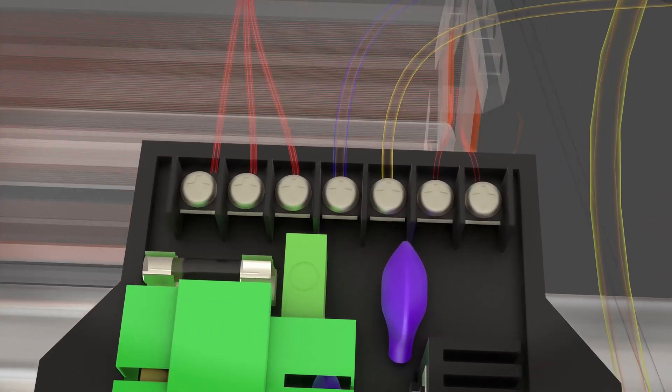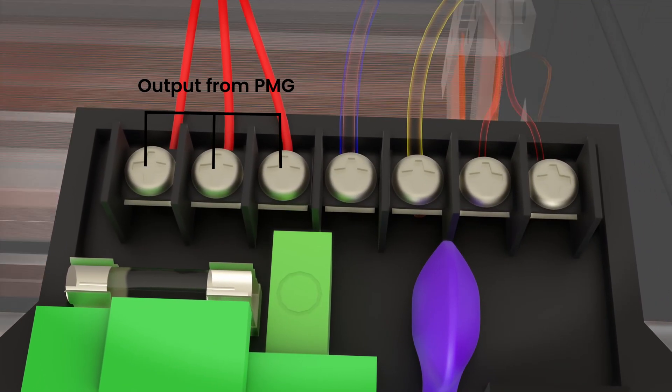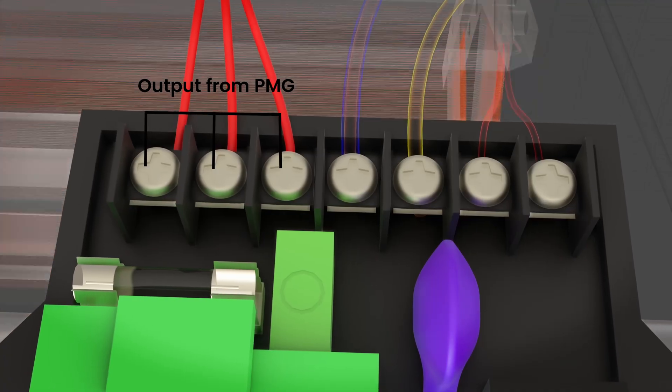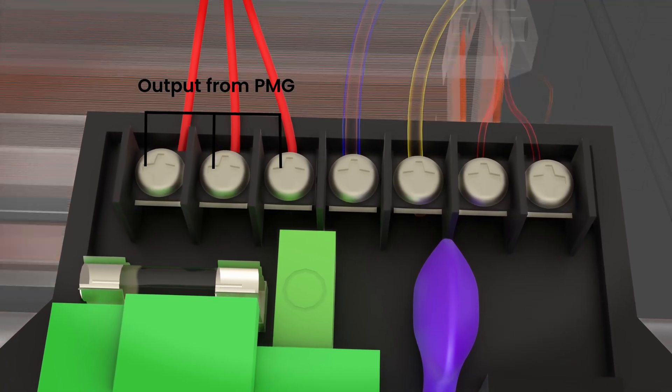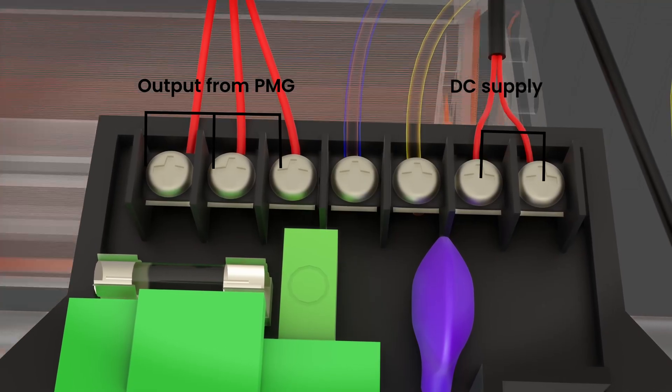The AVR receives three-phase electricity from the PMG. The AVR converts this three-phase AC electricity into regulated DC current using internal rectifier circuits. This converted DC current is supplied to the exciter stator field winding.